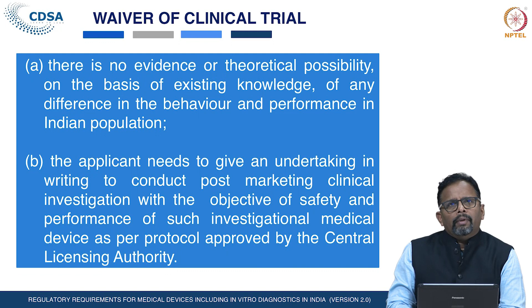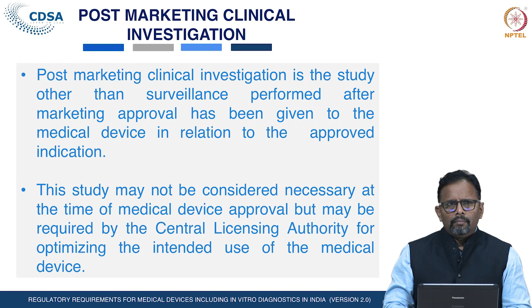The post-marketing clinical investigation is the study other than the surveillance performed after the marketing approval has been given to the medical devices in relation to approved indication. This study may not be considered necessary at the time of medical device approval, but may be required by the Central Licensing Authority for optimizing the intended use of the medical devices. The post-market clinical investigation includes additional drug device interaction, safety studies, and investigation designed to support use under the approved indications, subsequent to the approval of the investigational medical devices.